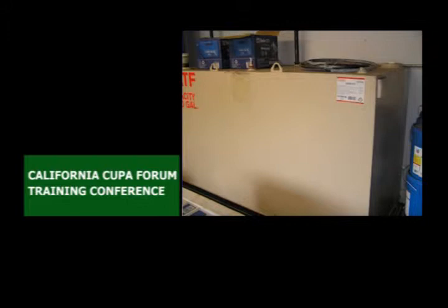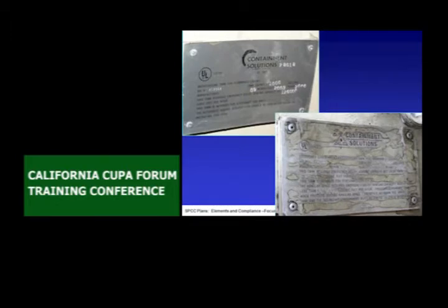Anyway, here's another tank. You people are unruly. Here's another tank, single or double wall. Maybe there's other fittings on top, but they're hidden by auto parts. It's a square tank, right? It looks like that. And there are some plan writers who will just write down that it's double wall. There are facilities that have no idea what the difference is. If you can see it, try and take a look at the plate. They're both by Containment Solutions. These are both UL listed tanks.